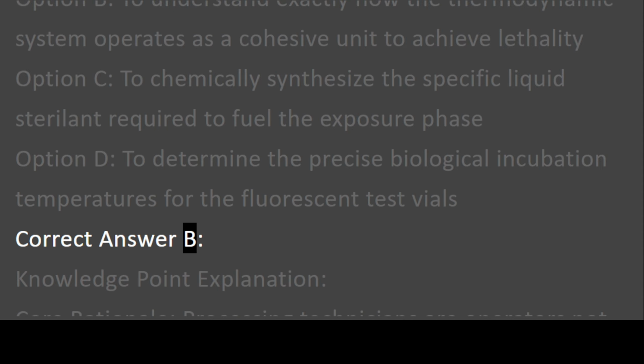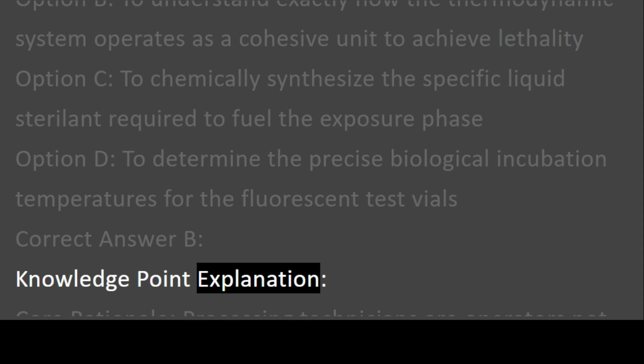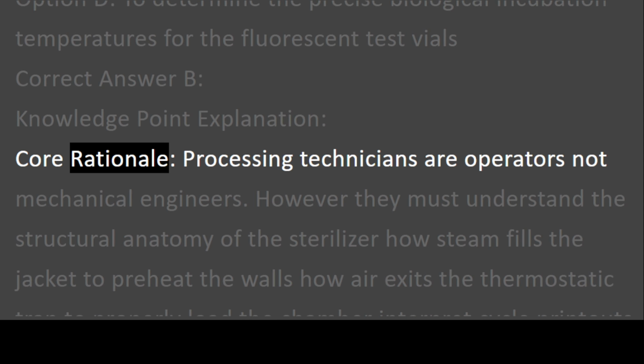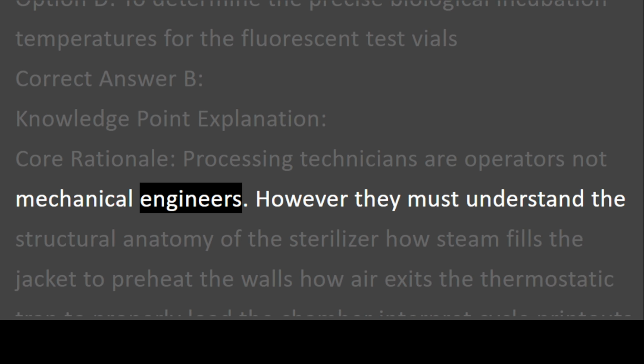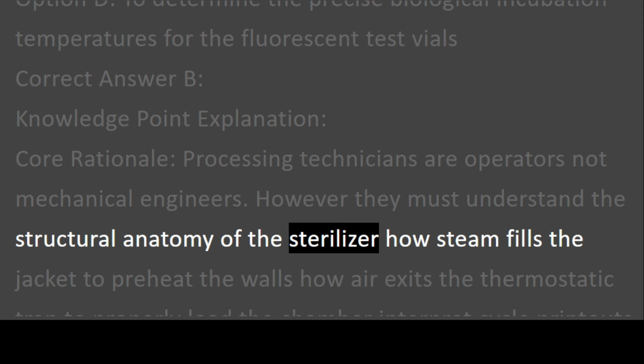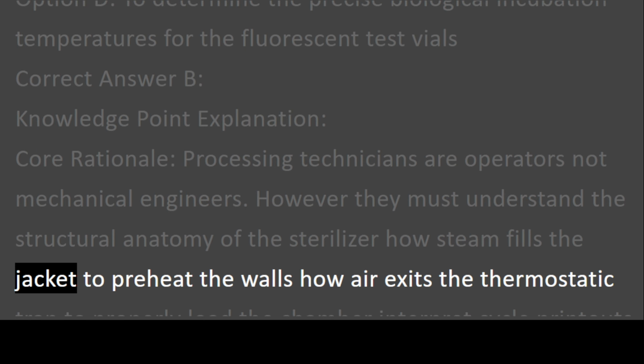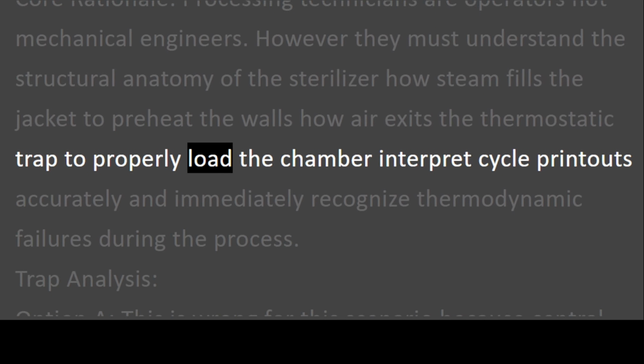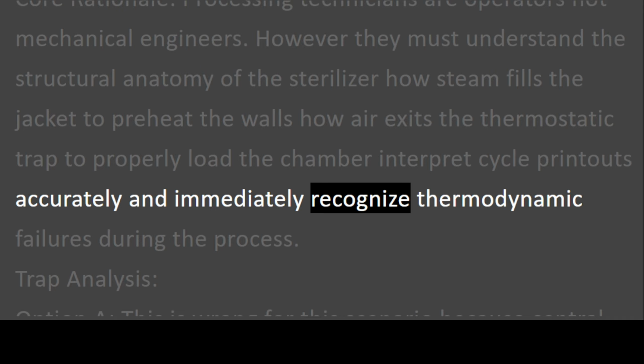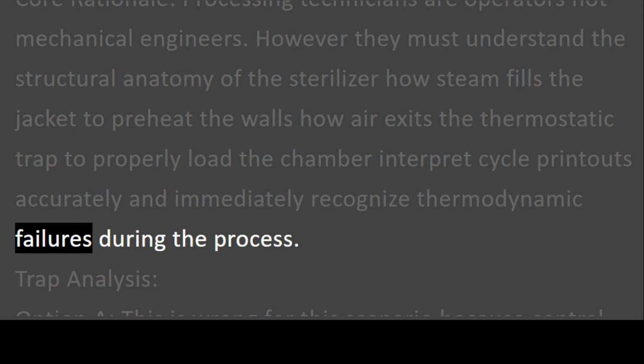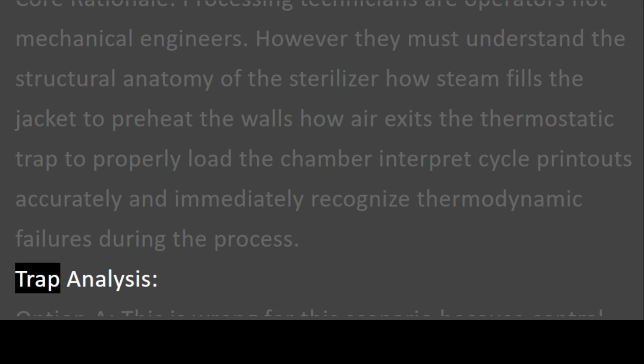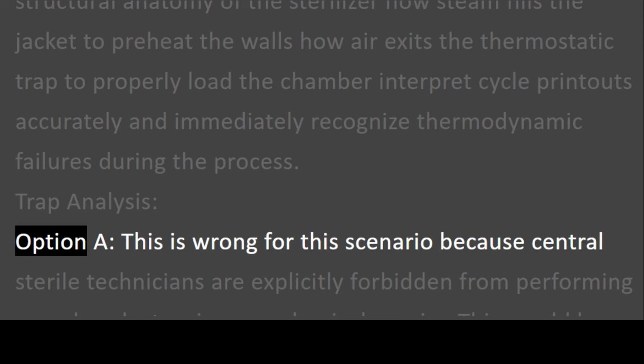Correct answer B. Knowledge point explanation. Core Rationale. Processing technicians are operators, not mechanical engineers. However, they must understand the structural anatomy of the sterilizer, how steam fills the jacket to preheat the walls, how air exits the thermostatic trap to properly load the chamber, interpret cycle printouts accurately, and immediately recognize thermodynamic failures during the process. Trap analysis. Option A.